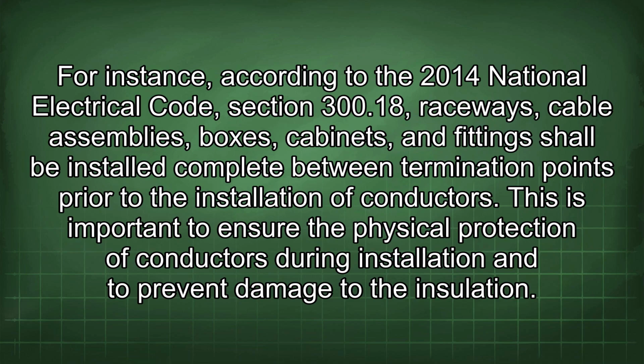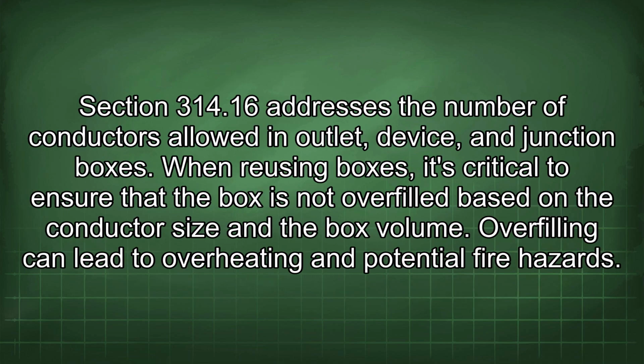For instance, according to the 2014 National Electrical Code, Section 300.18, raceways, cable assemblies, boxes, cabinets, and fittings shall be installed complete between termination points prior to the installation of conductors. This is important to ensure the physical protection of conductors during installation and to prevent damage to the insulation. Section 314.16 addresses the number of conductors allowed in outlet, device, and junction boxes. When reusing boxes, it's critical to ensure that the box is not overfilled based on the conductor size and the box volume. Overfilling can lead to overheating and potential fire hazards.